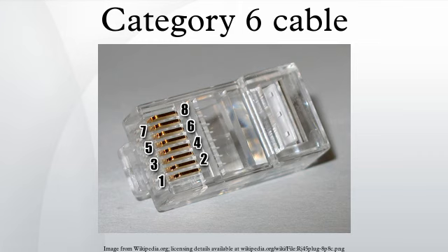The requirement for ground connections at both cable ends creates the possibility that a ground loop may result if one of the networked chassis has a different instantaneous electrical potential with respect to its mate. This undesirable situation may compel currents to flow between chassis through the network cable shield, and these currents may in turn induce detrimental noise in the signal being carried by the cable.